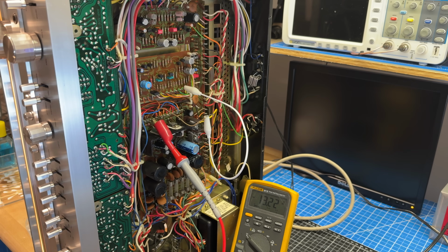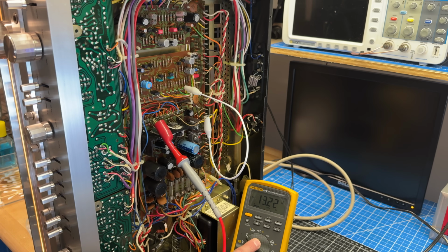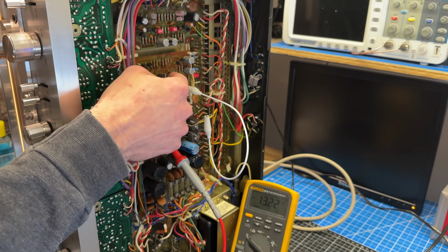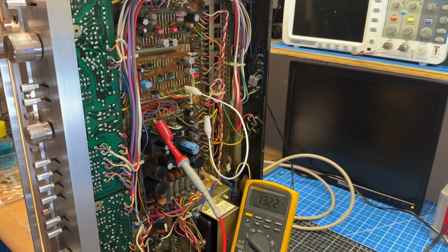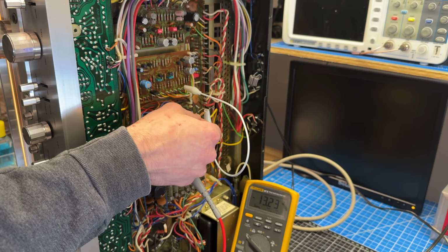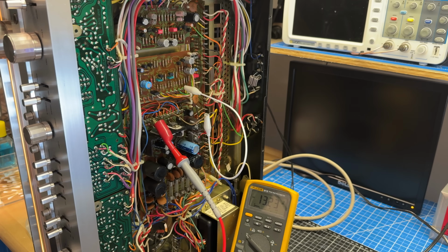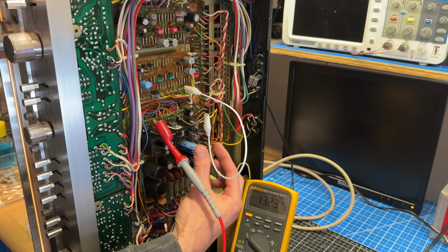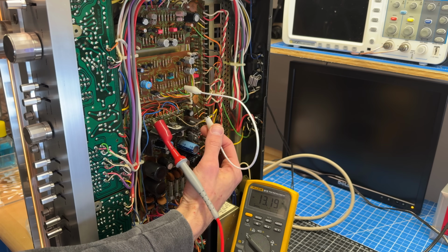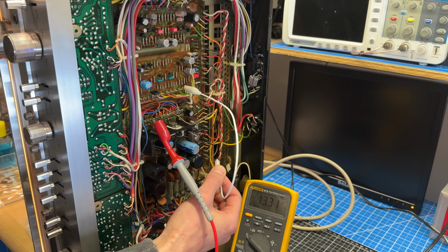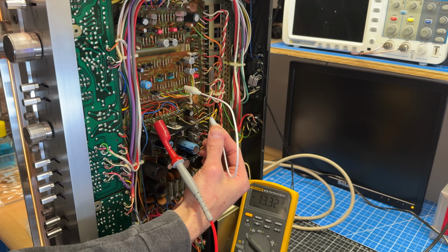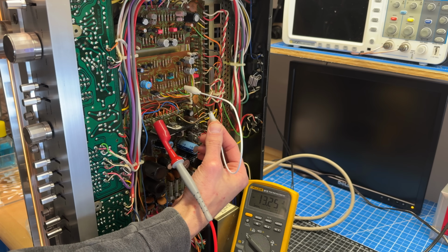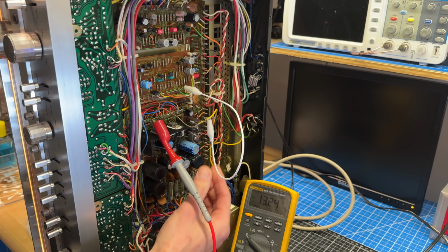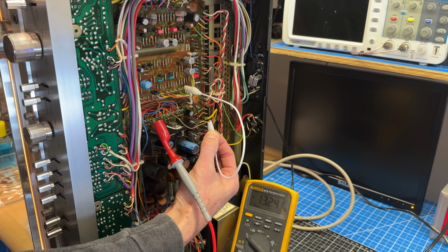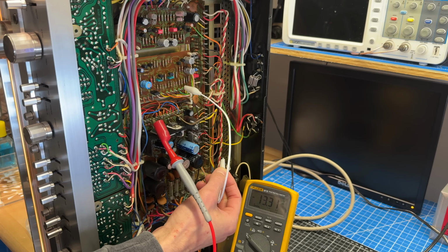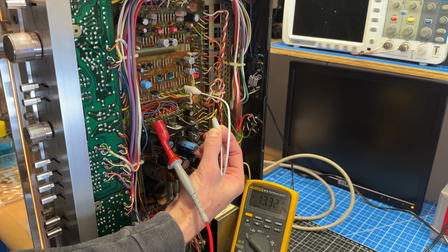After looking through the schematic, I found that this negative 13.5 volt supply's only function is to feed a portion of the protection circuit. So I've interrupted the connection from the power supply and temporarily connected it with a clip lead. If I go ahead and disengage the power supply - you may not have heard it, but the relay just disengaged - and there it comes back again. So I'm simulating our issue: if we lose that negative 13 volt supply, the relay conks out.